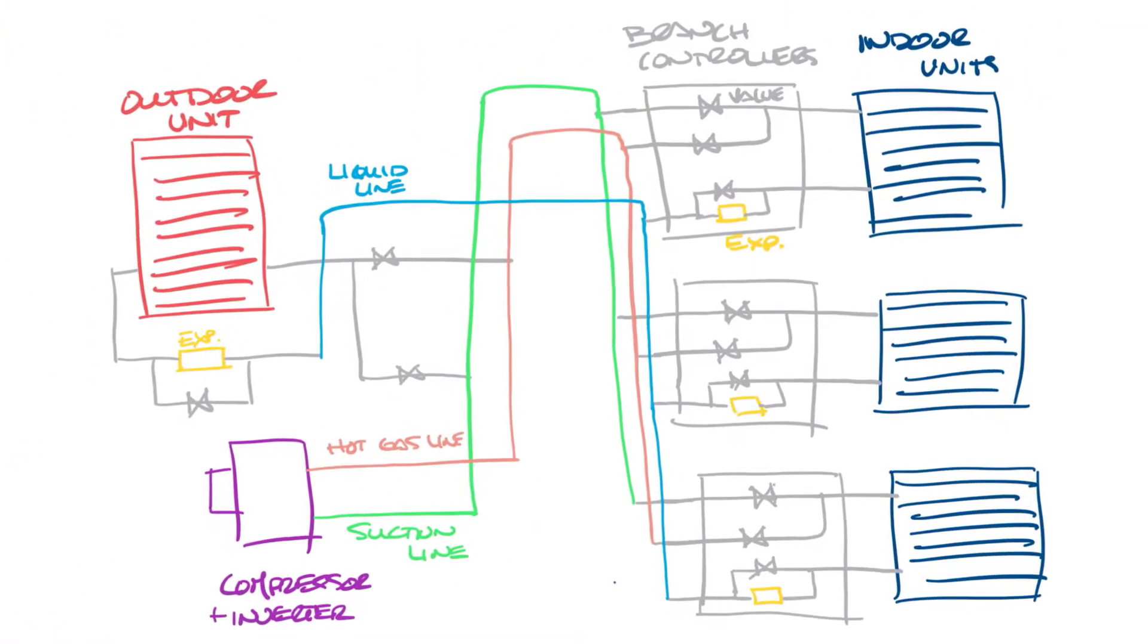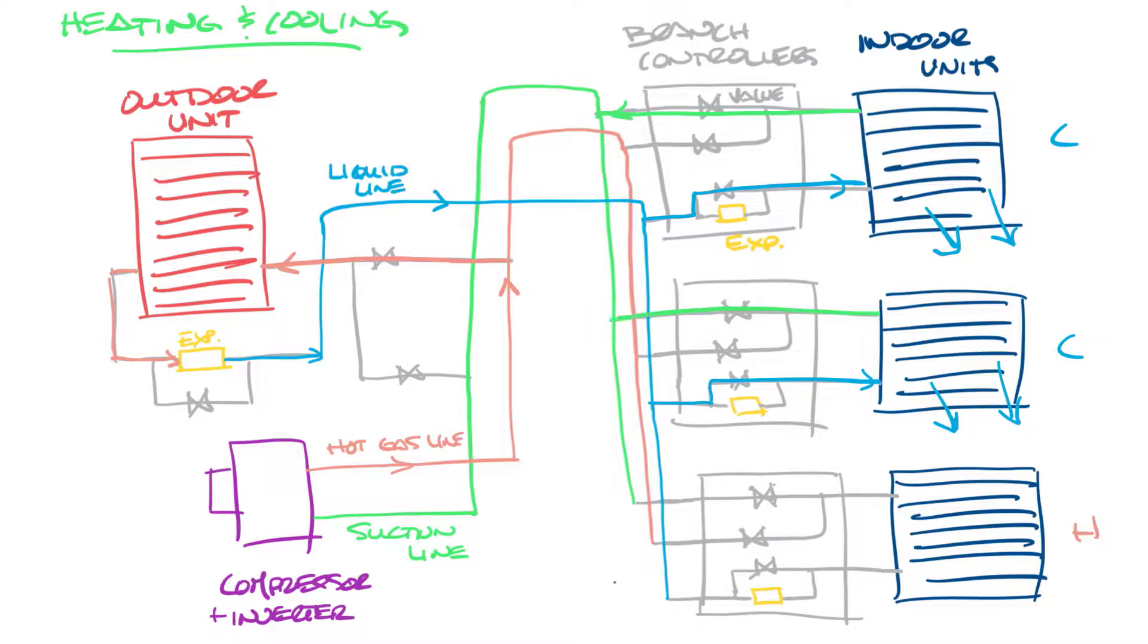But you can also heat some units and cool other units with a VRF system. So let's look at that. Let's say these top two units want cooling and the bottom one wants heating. Starting at the compressor, out the hot gas line, let's look at the cooling units first. So it's going to come in to the outdoor unit. Heat will be rejected. It'll go through the expansion device, be cooled down and flow into the two units that want cooling through the liquid line. And these spaces are cooled. It comes out of these two units, goes back to the suction line, and flows back into the compressor.